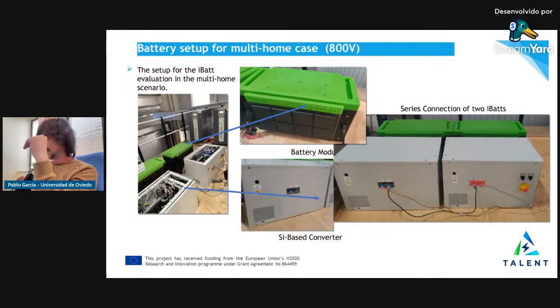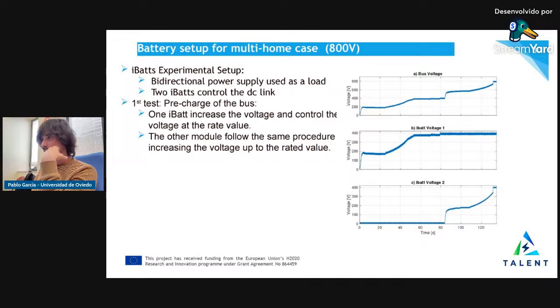We use a modified droop controller in the output for doing so. This adds a lot of flexibility. The bidirectionality of the two modules simultaneously allows, for example, moving energy from one to the other, such as when one has a lower charge than the other due to state of health. We can do that through the control system.